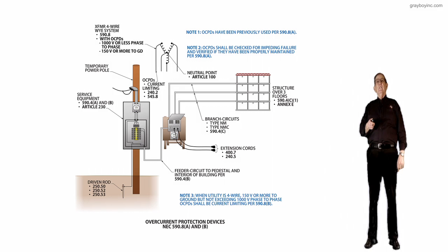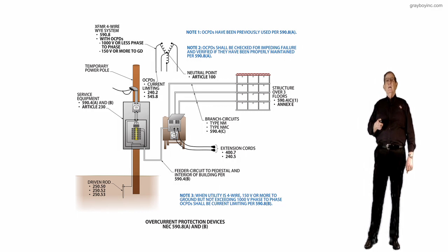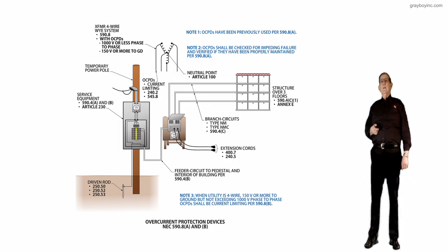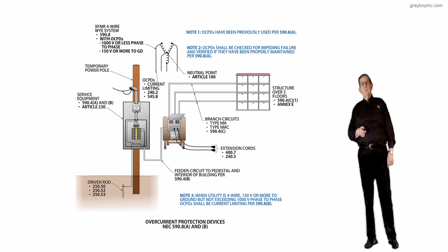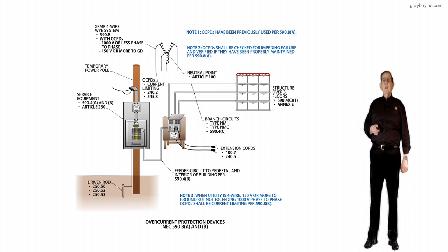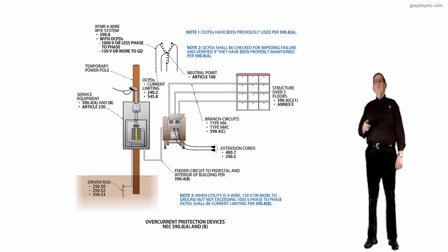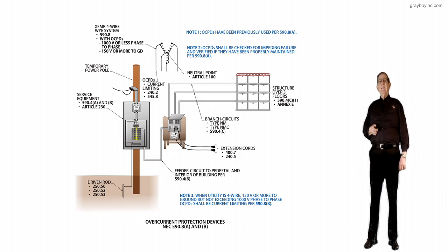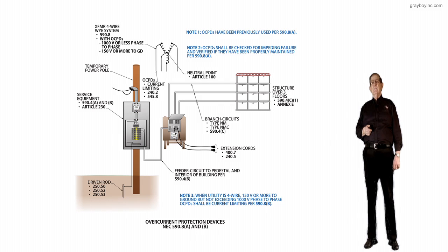Notice we have a transformer that's a 4-wire wye, 590.8(B), with overcurrent devices. 1,000 volts or less phase to phase, 480. 150 volts or more to ground, 277. Then notice the neutral points at the transformer. But notice we need current limiting type devices in this case.